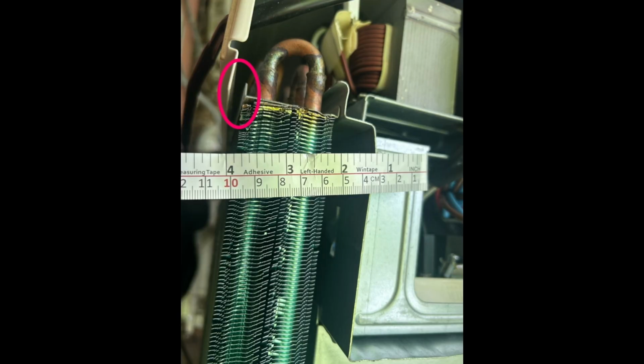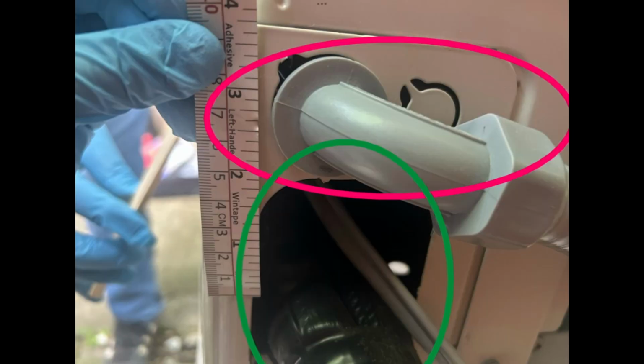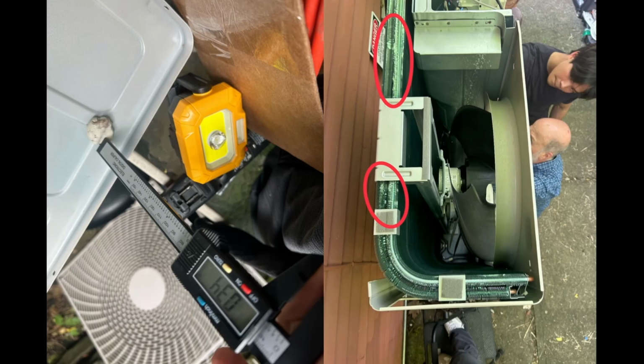Here is the long end. You can see the gap where it's circled. That's where air can bypass into the control compartment. This is the pipe and wire penetration holes, which is a pretty substantial bypass site in this unit. And here we measured the coil gap by squishing some putties and measuring how thick the putty is, which will show how much of a gap there is between the top cover and the coils.